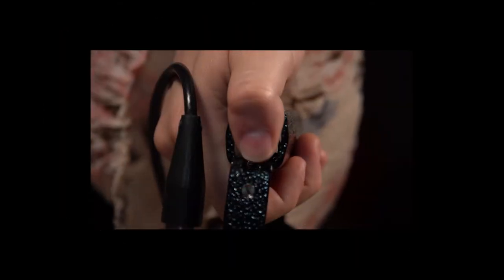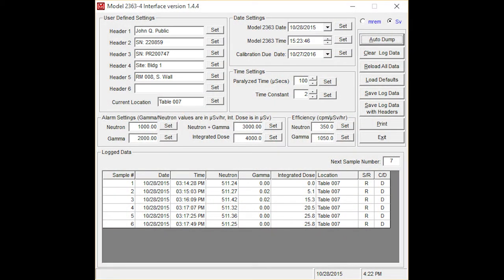The Model 2363 can log up to 1,000 data points in non-volatile memory. Each data point consists of the sample number, a date-time stamp, rate meter measurements of both neutron and gamma, and integrated dose measurements of both neutron and gamma.